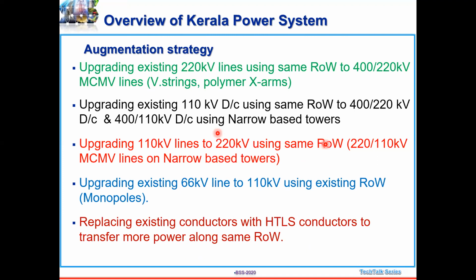That is the first time in India that one single circuit 220 kV right of way is used for upgrading to 400/220 kV. It's the first time in India, even PGCIL has not done that. KSEB has designed towers for using the same 22-meter right of way. Normally, we require 46 meters of right of way for 400 kV, but here we use only 20-25 meters for establishing this 400/220 kV network without any additional acquisition of land. We use V strings and polymer cross-arms for that. That's almost a first-time thing. Then we use the existing right of way of 110 kV DC lines also for upgrading to 400/110 kV DC. That is under construction now.